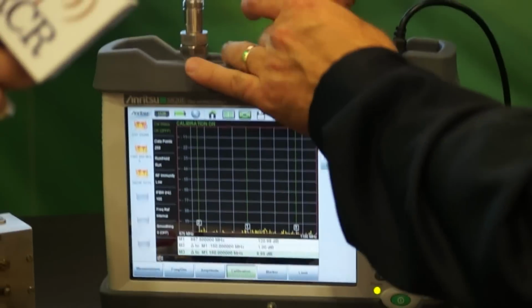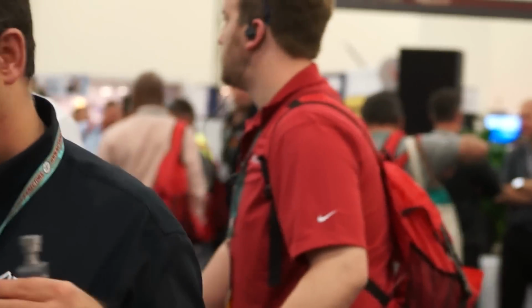Another feature that this instrument offers is the ability to make 2-port transmission measurements on devices that are far away from the instrument itself. By using this sensor and these special adapters, we put a piece of Ethernet cable in between, and we're able to extend this up to 85 meters, which is 278 feet, away from the instrument. This comes in handy for measuring cables that are already embedded into systems that cannot be easily accessed from both ends. Aircraft wings, aircraft fuselage, Navy ships, those types of things, where these cables need to be regularly measured, but they're not easy to get at both ends of. So this is a unique feature on the SiteMaster that gives users the ability to measure those, not just at a single frequency, but swept across an entire range.